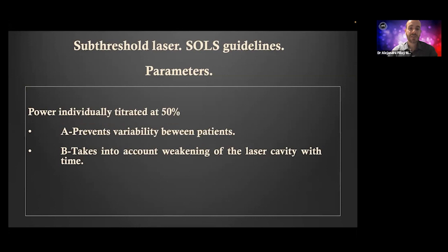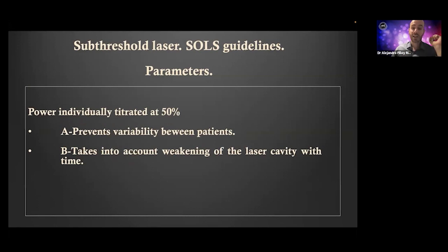Regarding power, here some degree of disagreement begins. Our publication recommends titration, though many specialists treat today with fixed powers and with good results. By titration, we mean individually calibrating the energy necessary for every case. We do this by placing single spots in the peripheral healthy macula until we see a minimally visible burn, then working at 50% of that power. Titration prevents variability between patients — lightly pigmented patients absorb less energy — and accounts for laser cavity weakening over time. But many good specialists work without titration with good results, so it's not perhaps the most important point.